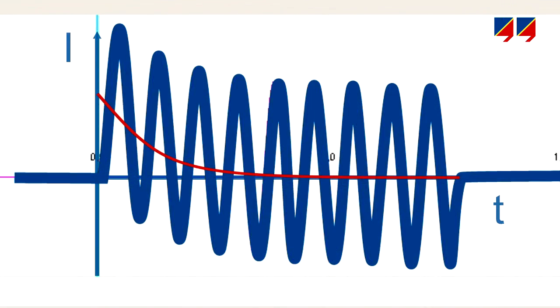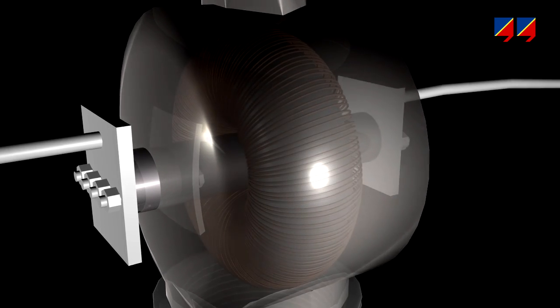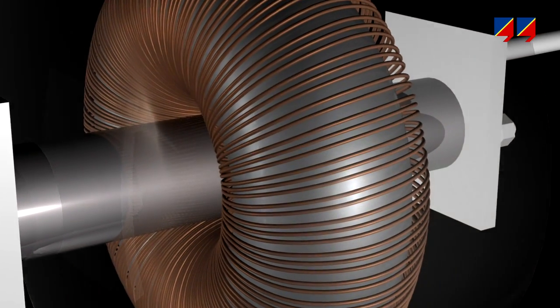The DC component of short-circuit fault currents is particularly important, as it may lead to high levels of magnetic flux in the CT core.